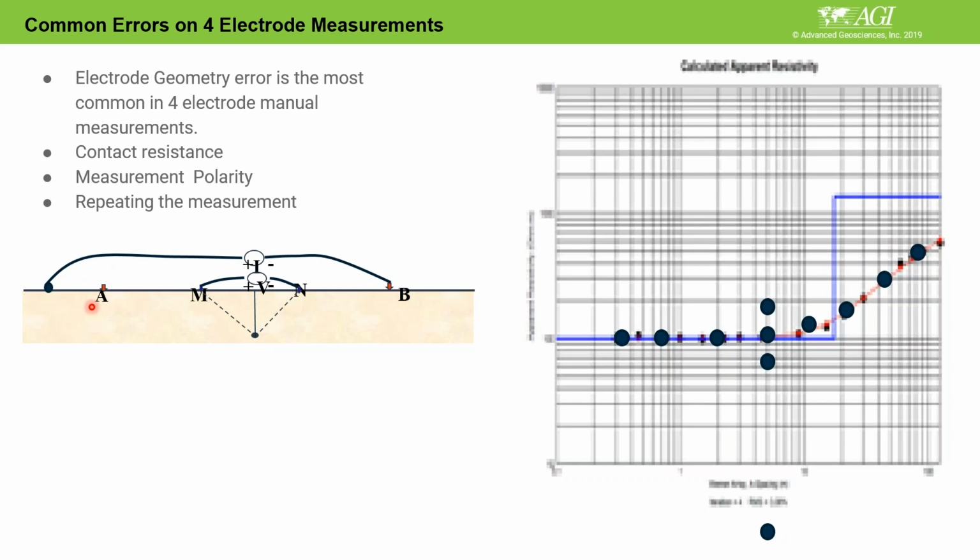Even if we recommend repeating that measurement, that means the default setting does two measurements, and then gets a standard deviation of the 2 measurements. If the error is less than 2%, it permits you to go to the next one. If it is more, then you repeat that measurement. In this case, sometimes you don't get an error on the measurement. So you really get, okay, a very good result. I mean, a very good measurement.